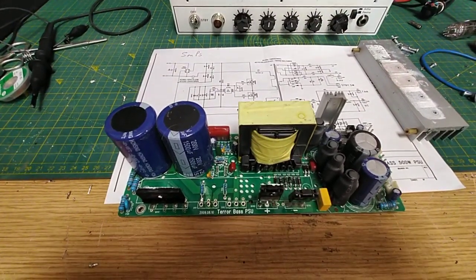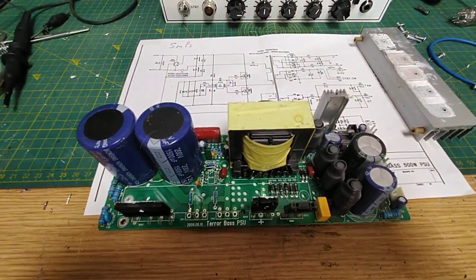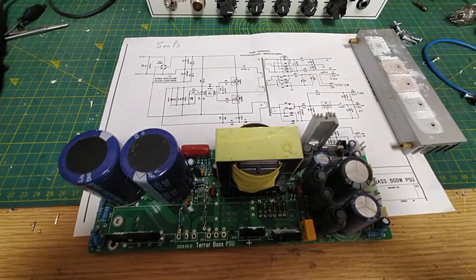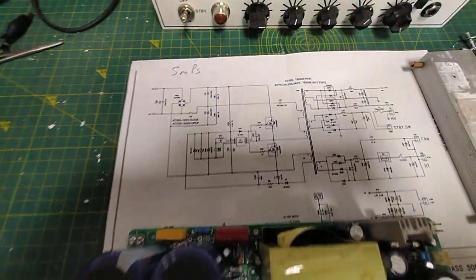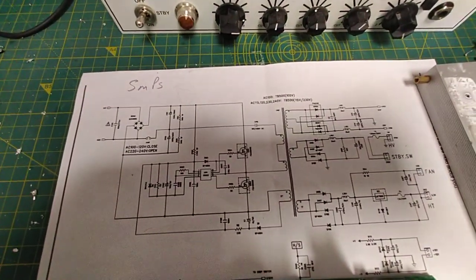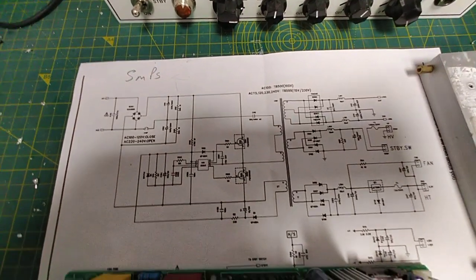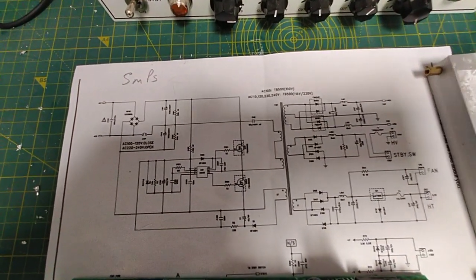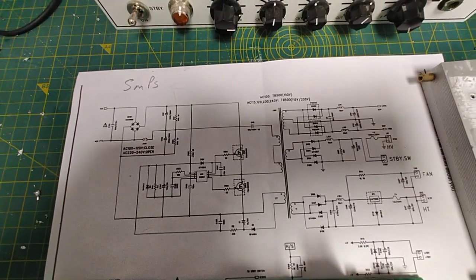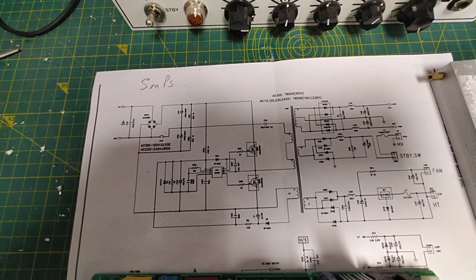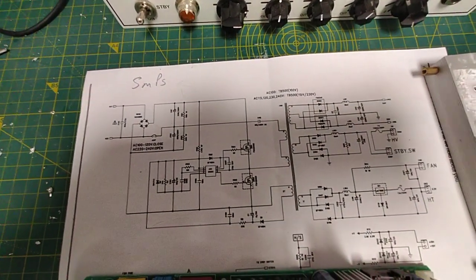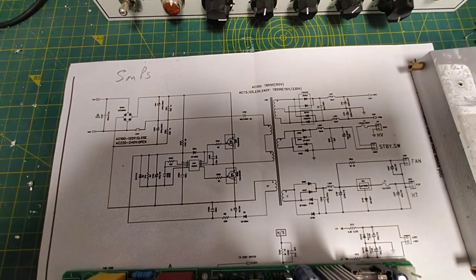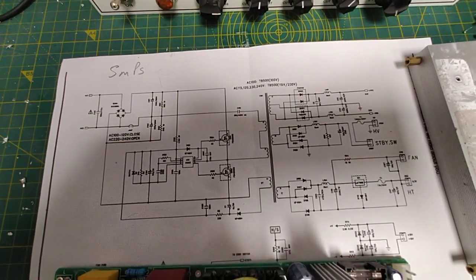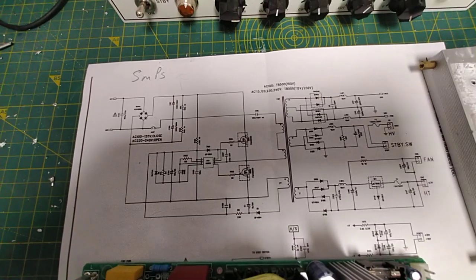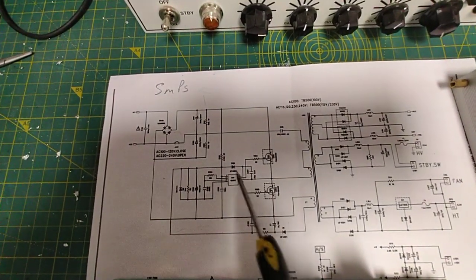But this is the power supply which is in trouble, and it's a switch mode power supply. Now these run probably around 30, 40, maybe 50 kilohertz, and you do have to change your servicing approach to them slightly. Whereas a conventional power supply has a transformer with secondaries that are rectified and filtered, with these you have a primary section.